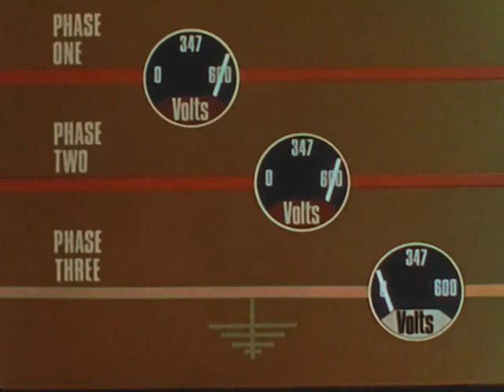Often, several installations, even in separate buildings, are fed from a single three-phase transformer over the same delta circuit. This can sometimes present a problem should a ground fault develop in one building. As illustrated in the previous diagram, the building where the fault occurs has a voltage drop to 0 on the faulty phase, while the remaining buildings experience a rise to 600 volts to ground on the phases not affected by the fault in Building D.